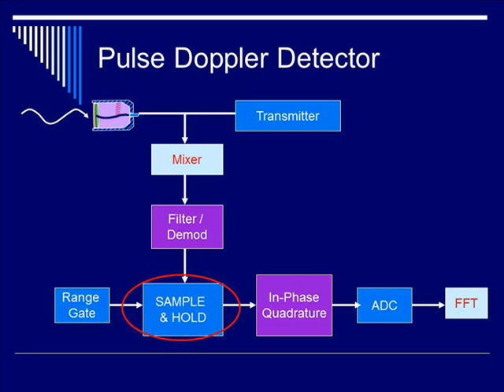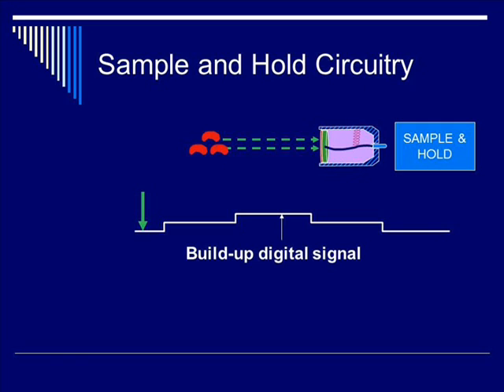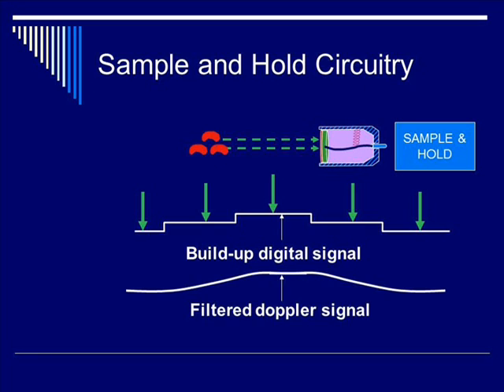Let's talk about the sample-and-hold. As the name suggests, you're sampling the analog signal and building up the signal inside a hold circuit. As blood cells reflect velocities back to the transducer and into the detection system, you gradually build up the digital signal, as indicated by the green arrows. As signals are built up during each sampling period, they are digitized and converted via smoothing into a filtered Doppler signal.